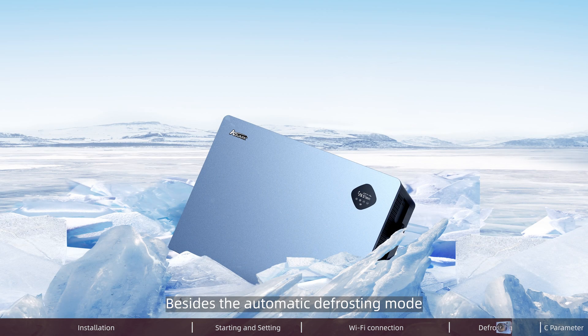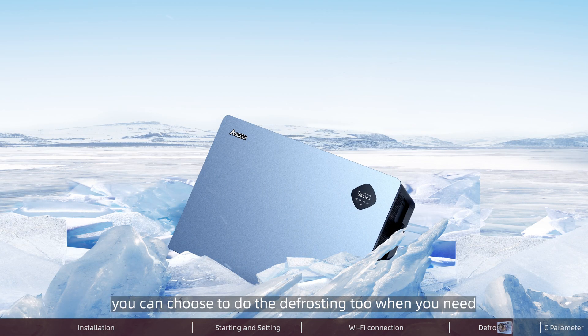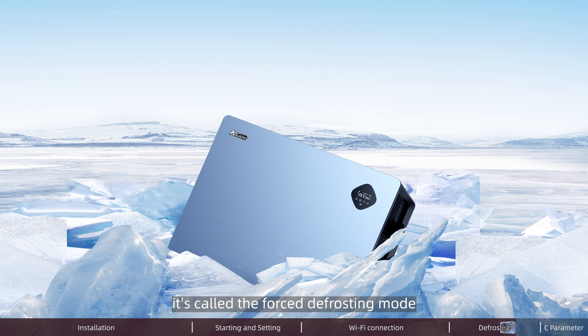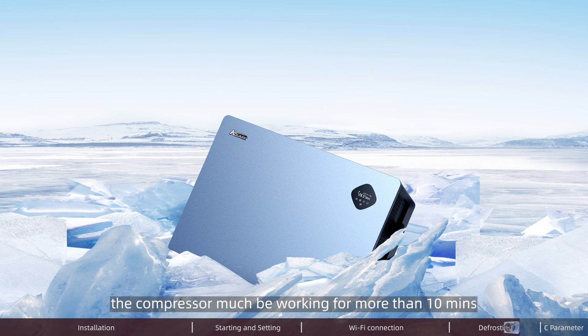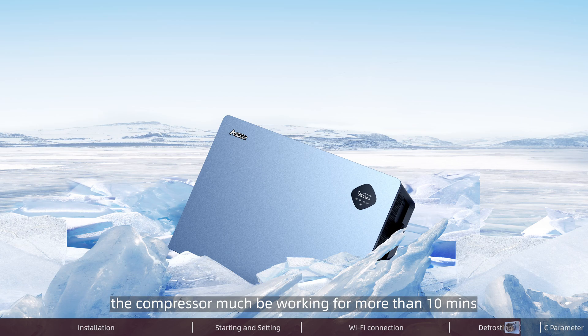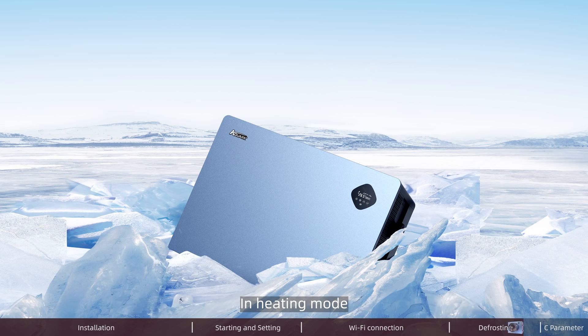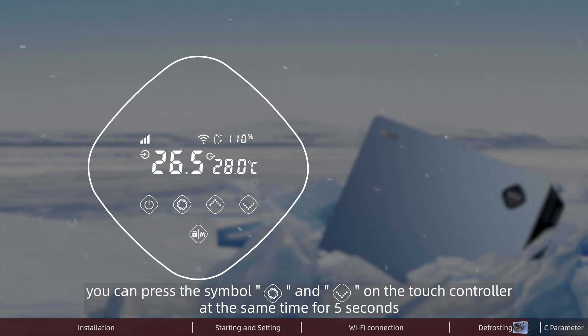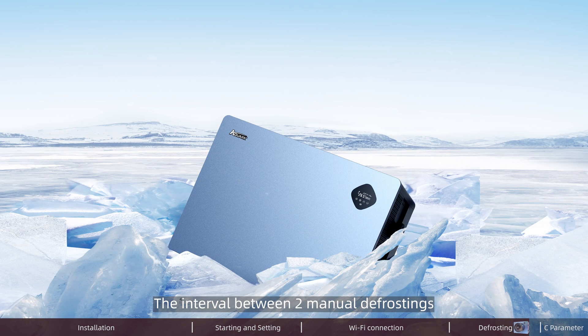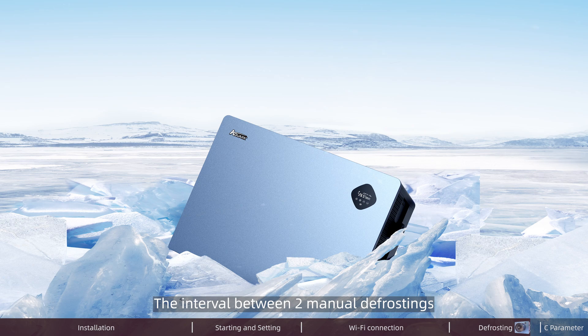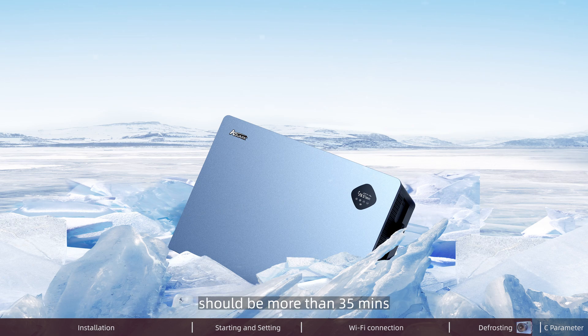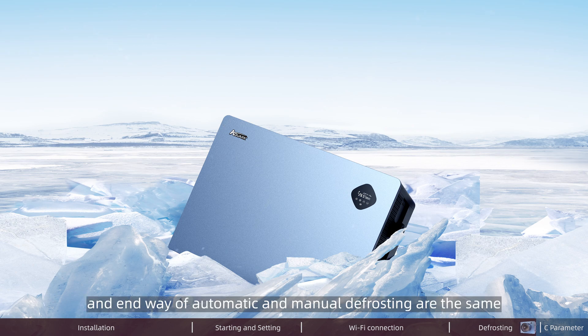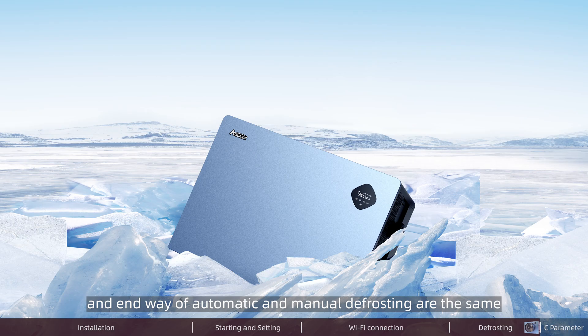Besides the automatic defrosting mode, you can choose to do the defrosting manually when you need. It's called the forced defrosting mode. To enter the forced defrosting mode, the compressor must be working for more than 10 minutes. In heating mode, you can press these two signs on the touch controller at the same time for 5 seconds. The interval between two manual defrostings should be more than 35 minutes. The working principle and the end way of automatic and manual defrosting are the same.